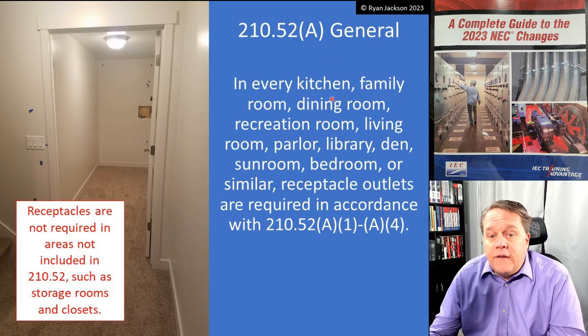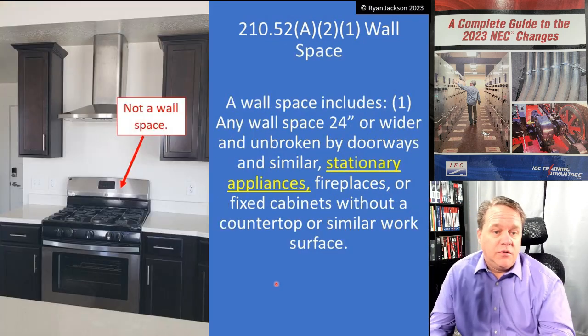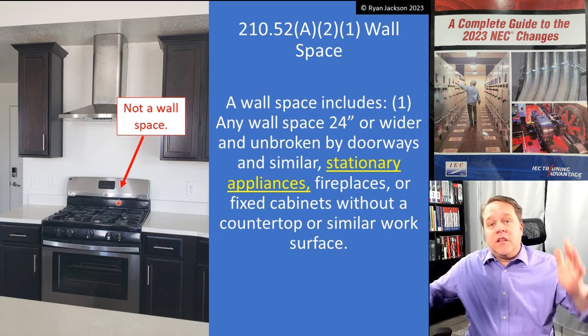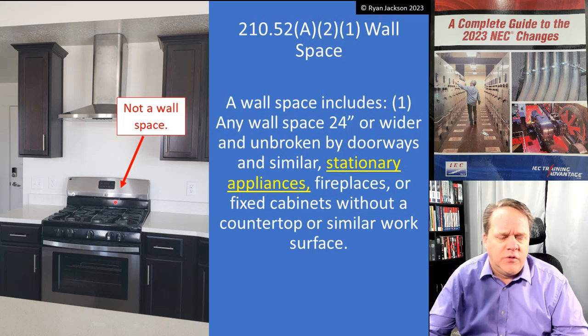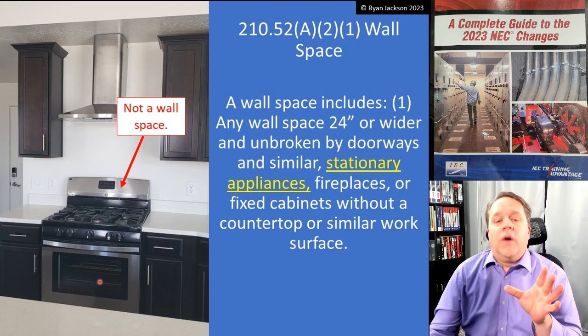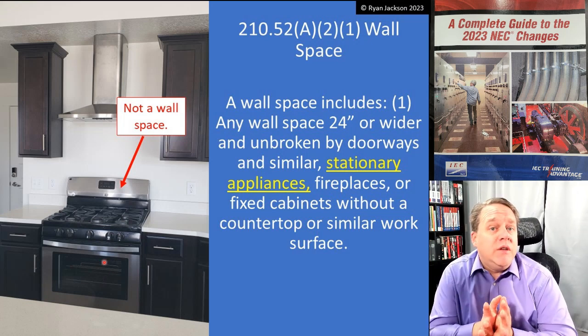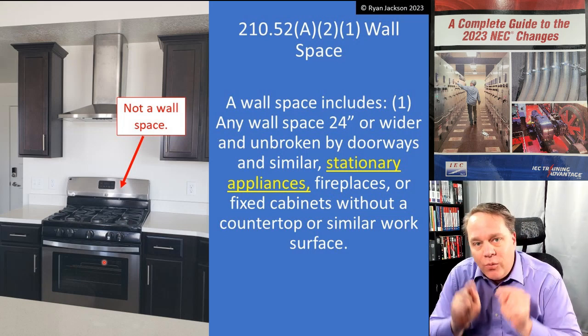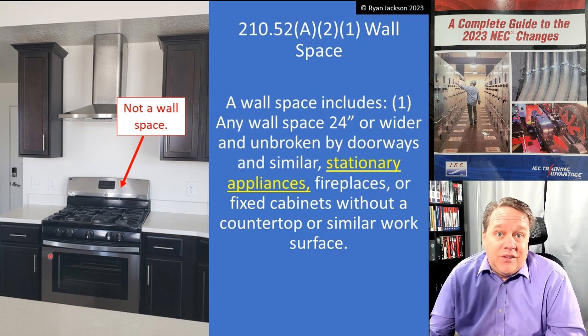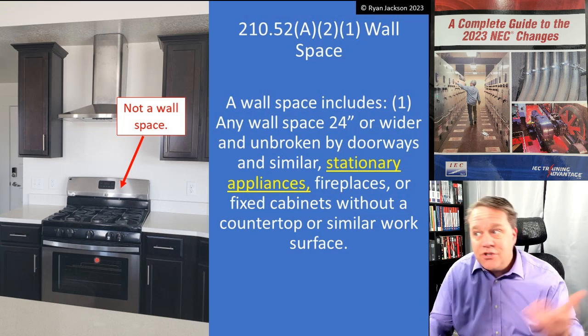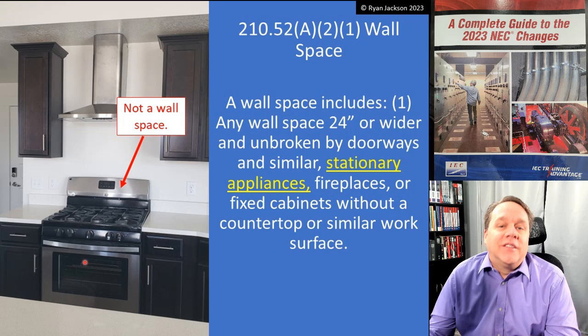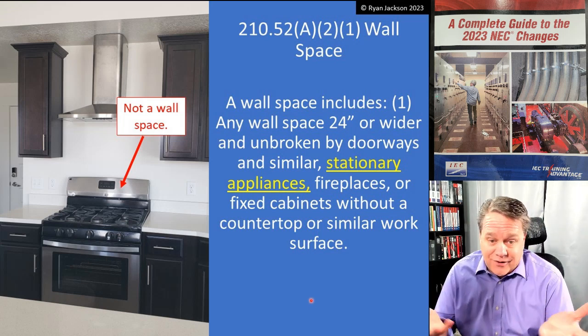210.52A requires regular wall-space receptacles in every kitchen. If you remove the range, that gap between two countertops is not wall space — you wouldn't need a receptacle there to satisfy 210.52A. In previous code versions, you could argue the space behind a range was still wall space. Now it's very clear: space consumed by stationary appliances is not considered wall space. That's probably a good clarification.